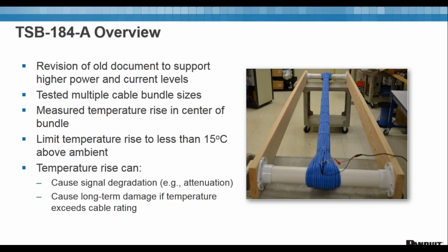And you can see here we're injecting current on all 4 pairs to correspond to the different power levels, the Type 3 and Type 4 power levels. We make these cable bundles different size, so different amount of cables in each bundle. And we have thermocouples in the center of those cables to see how hot the cables get.